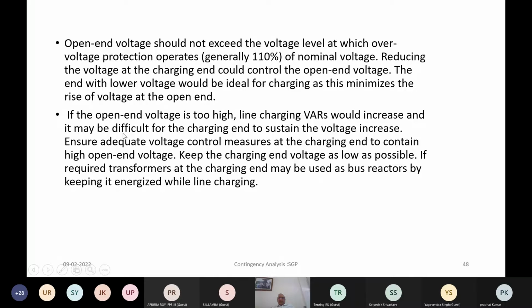So when you have the open end voltage too high, you charge the line at one end and the remote end voltage is too high, then charging of the lines, that means reactive power which is leading, it may be difficult for the generator to survive with the over voltage. In that case, reactors and other control measures should be kept in service so that you don't face this. So you line up the reactor and then charge the line with reactor already connected to the line. So dead line along with reactor you can charge.